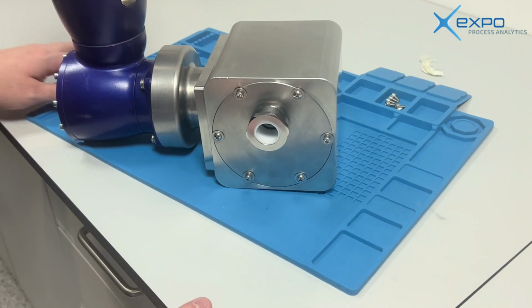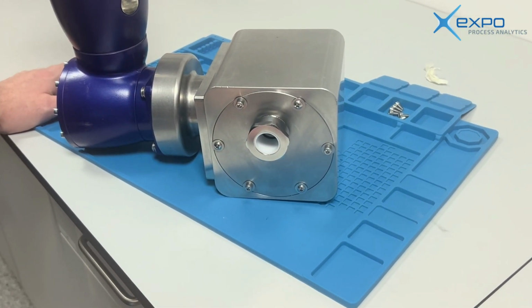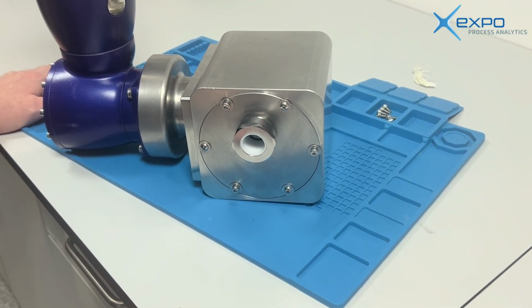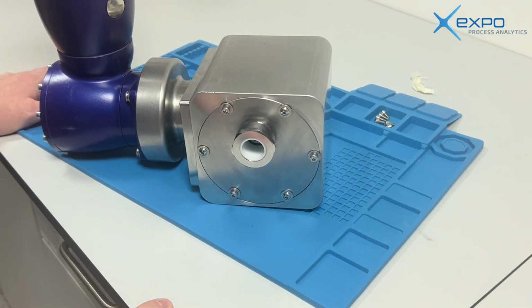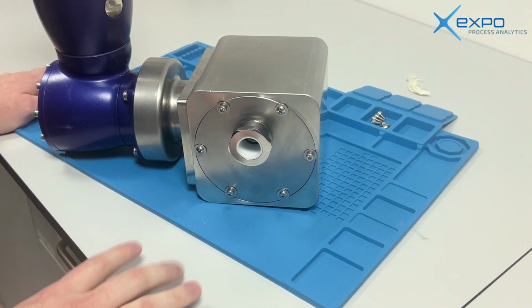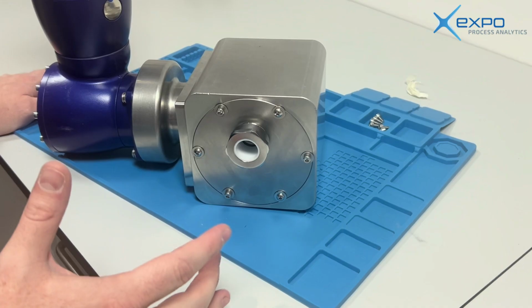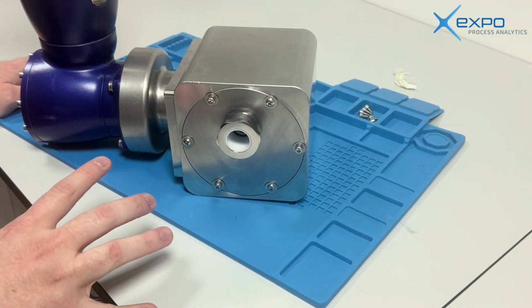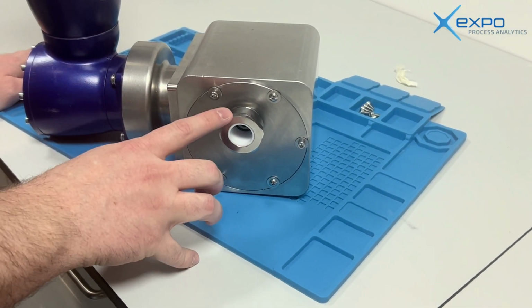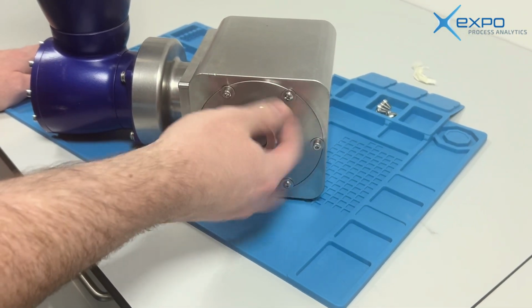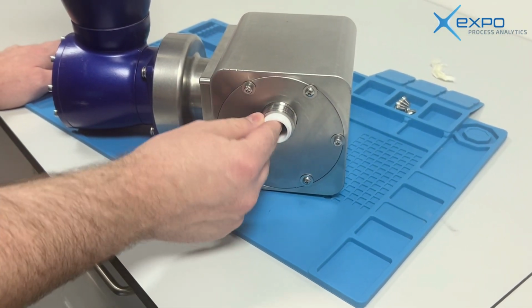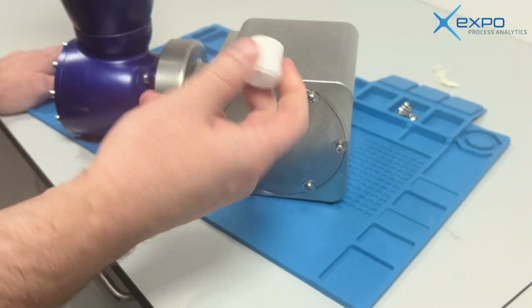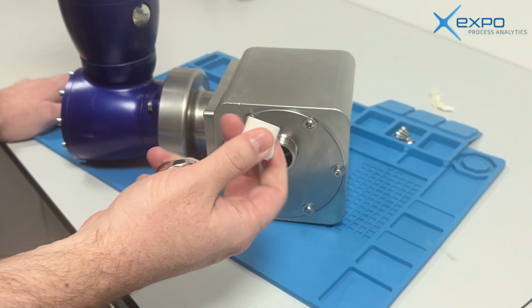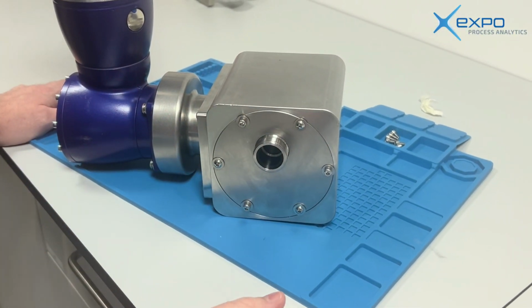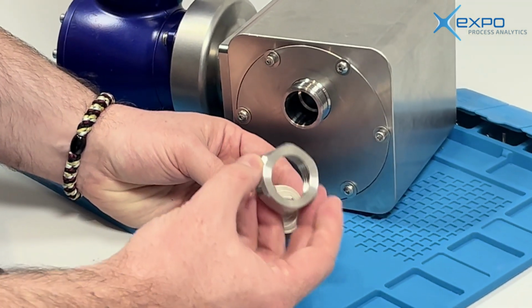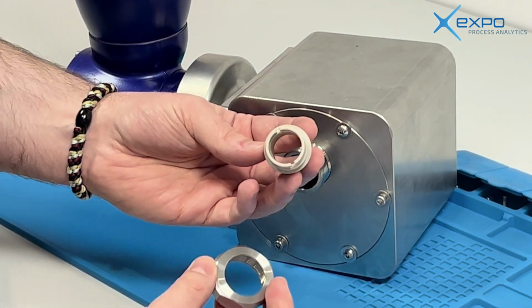Okay, so this is a video to use the probe setting tool with the Expo process analytics devices. For any devices supplied from 2025 onwards, they will be supplied with the new compression fitting. For any legacy devices prior to that, they will have this old fitting. All you need to do is unscrew the retaining nut, pull out that compression sleeve, and then we can install the new one. Okay, so you're going to start by fitting the locking nut over the compression sleeve.